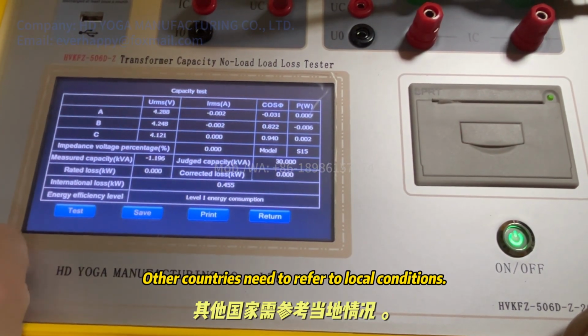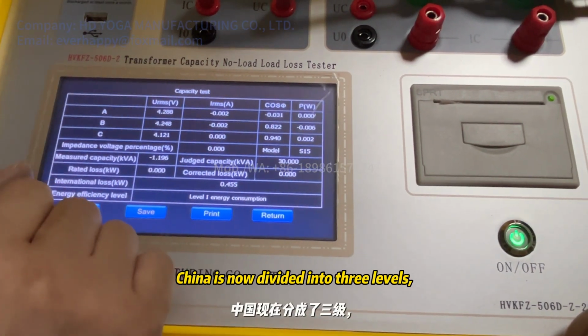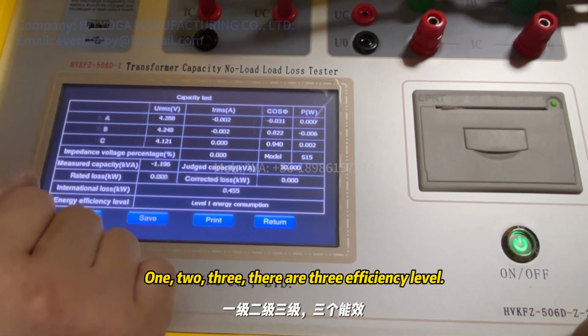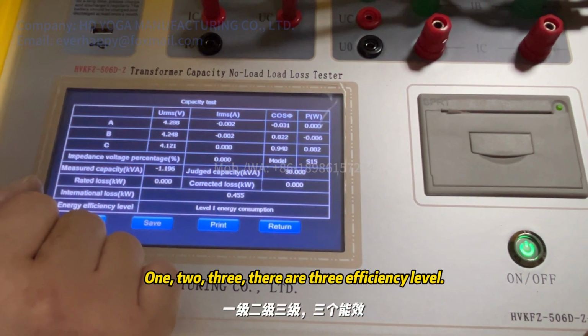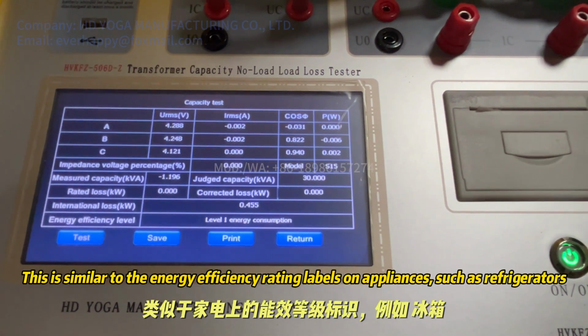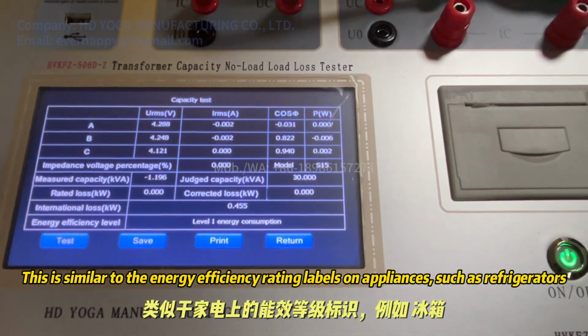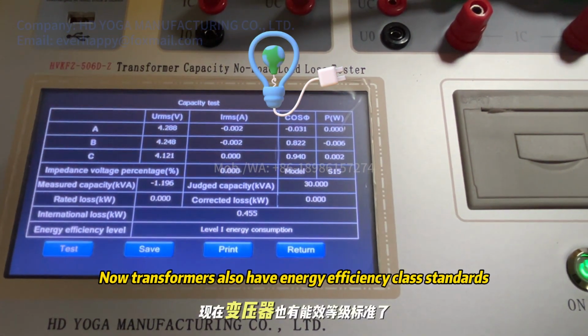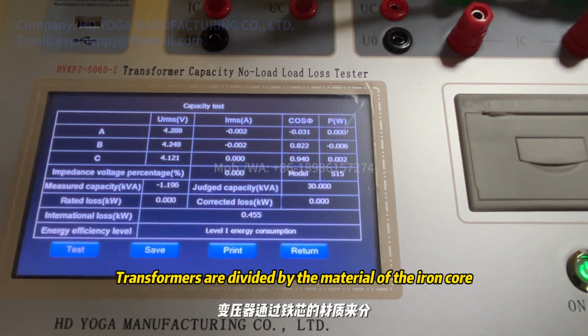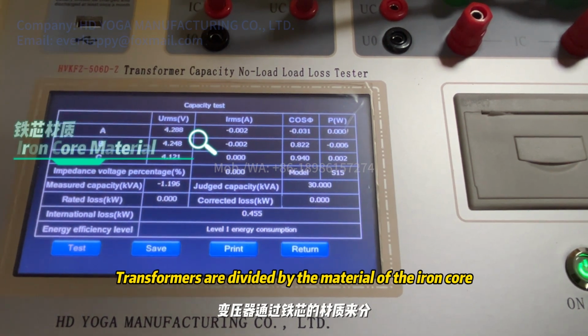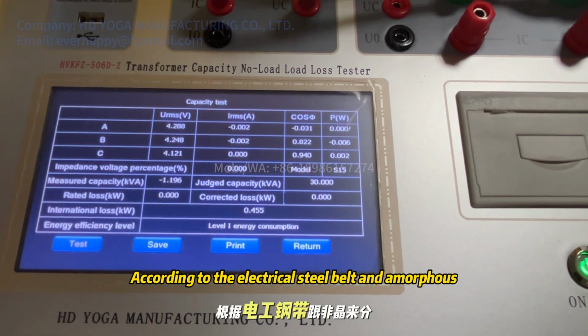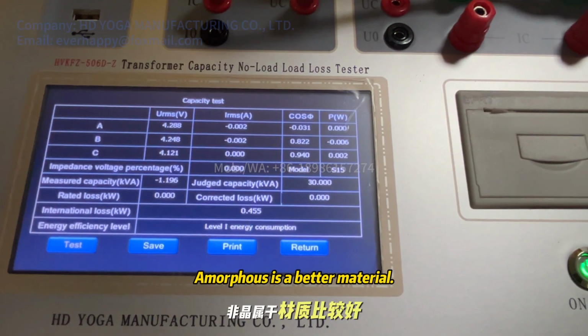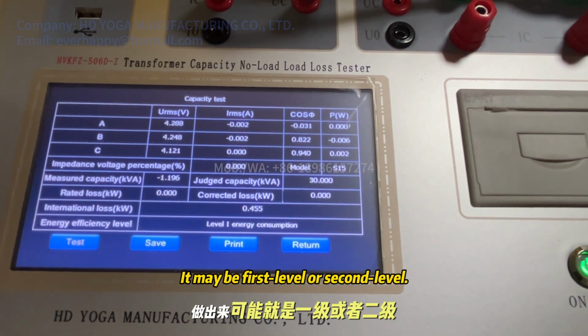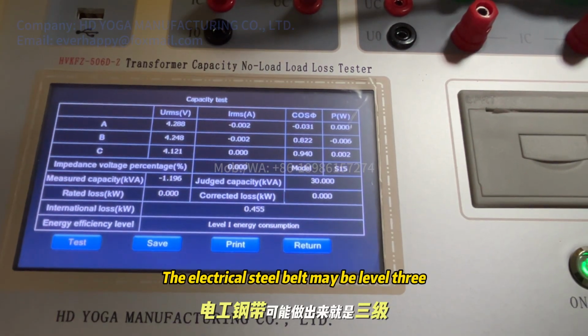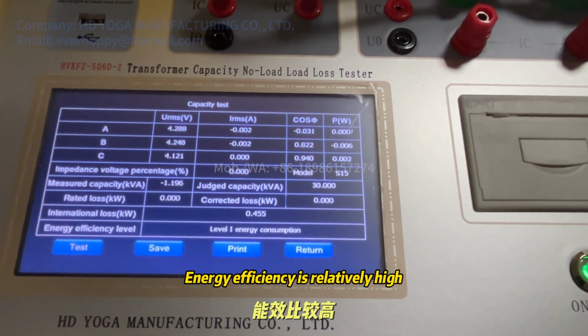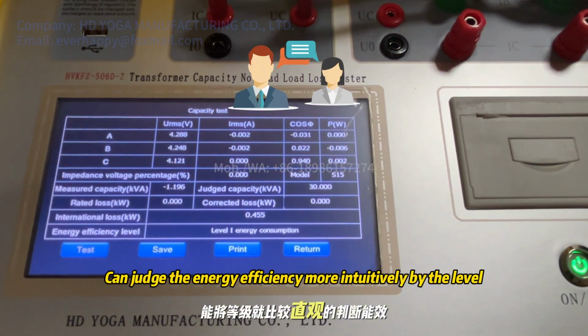Other countries need to refer to local conditions. China is now divided into three levels. One, two, three. There are three efficiency levels. This is similar to the energy efficiency rating labels on appliances, such as refrigerators. Now, transformers also have energy efficiency class standards. Transformers are divided by the material of the iron core, according to the electrical steel belt and amorphous. Amorphous is a better material. It may be first level or second level. The electrical steel belt may be level 3. Energy efficiency is relatively high. Can judge the energy efficiency more intuitively by the level.